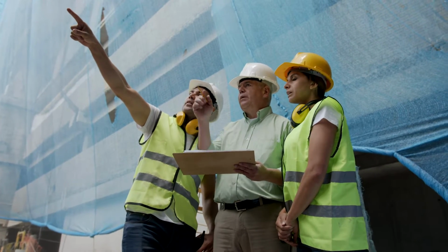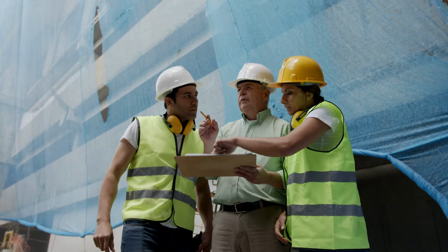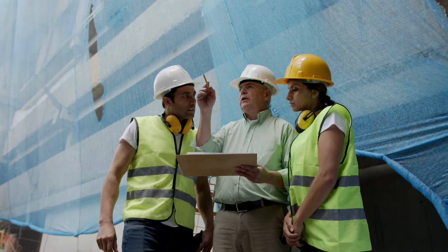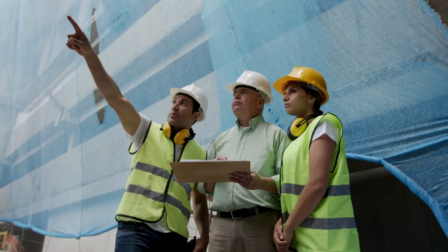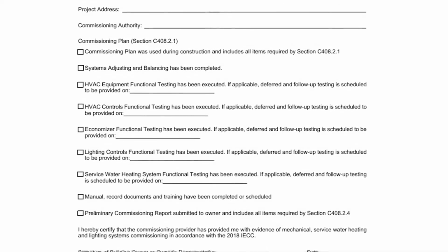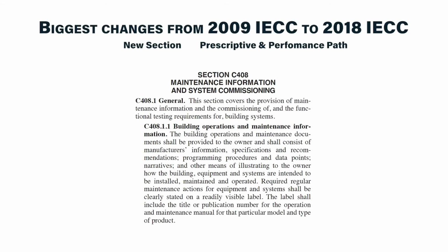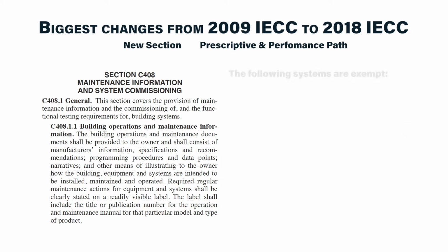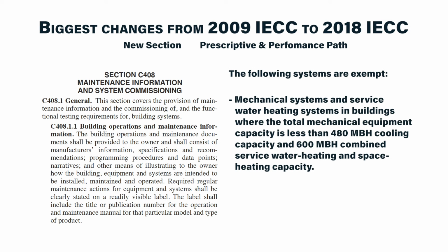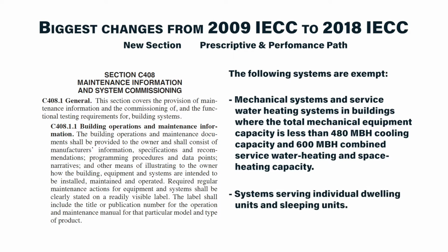Having a comprehensive commissioning plan helps ensure that the building HVAC and lighting controls are programmed correctly and operate as intended. A commissioning checklist is always handy in the field. Note that mechanical and service water heating systems with capacities less than a certain threshold are exempt from the commissioning requirement. Systems serving individual dwelling units and sleeping units are also not required to complete commissioning. Refer to the code for additional details.